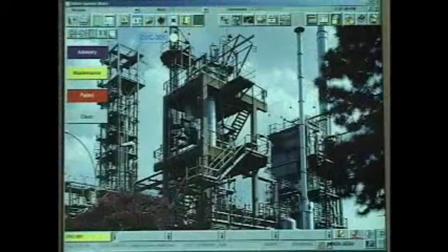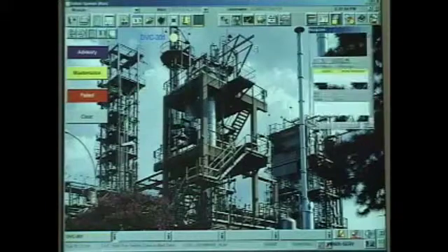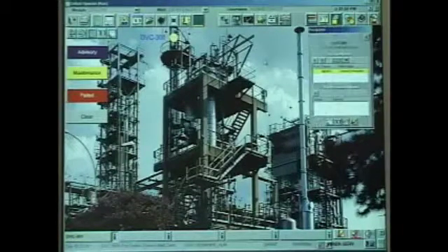And you'll see that the device alert, DVC 301, appeared here. Now at the operator's console, I can look at the faceplate for that. You'll see here that we had a travel deviation. That's because I moved the valve indicator position without the valve itself actually moving. Now that information was actually generated down in the device and passed all the way up here.